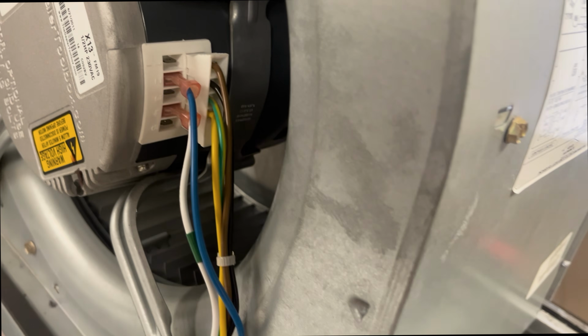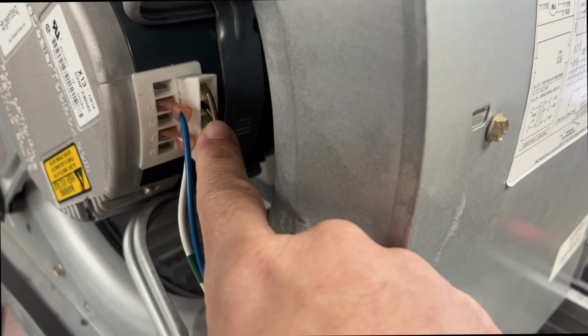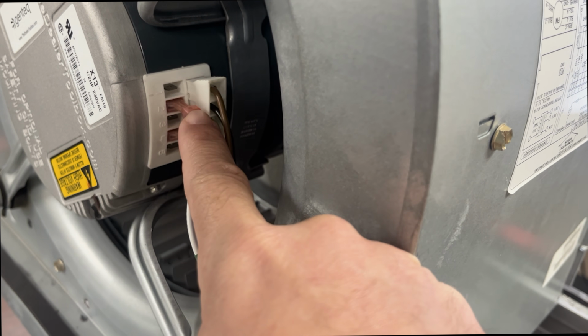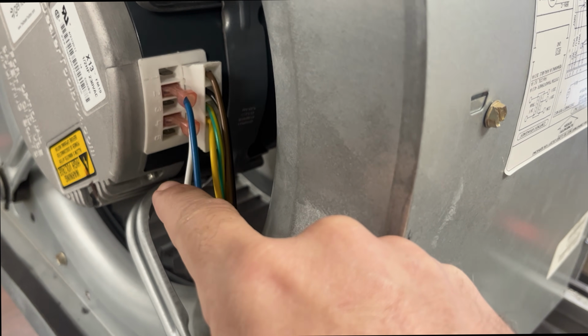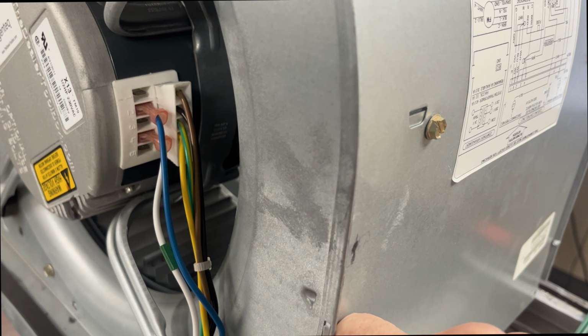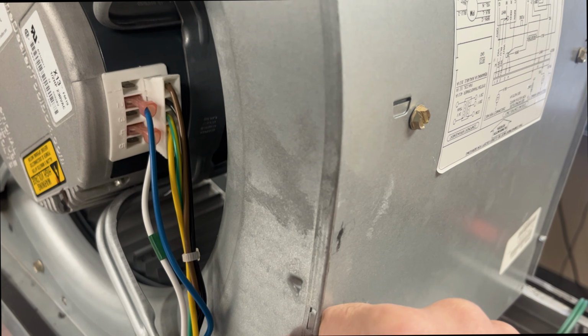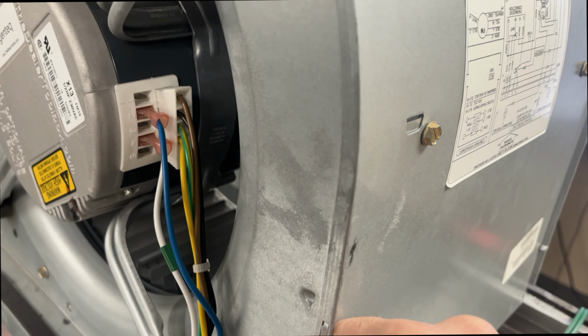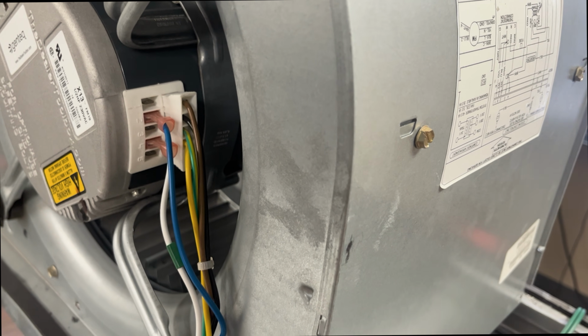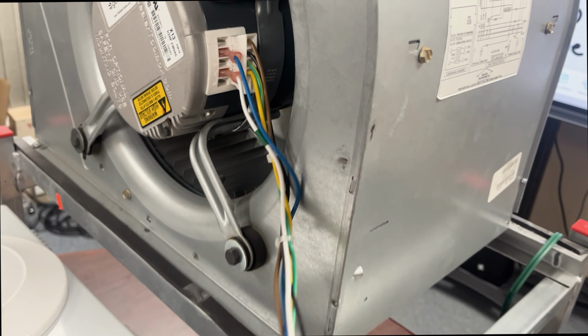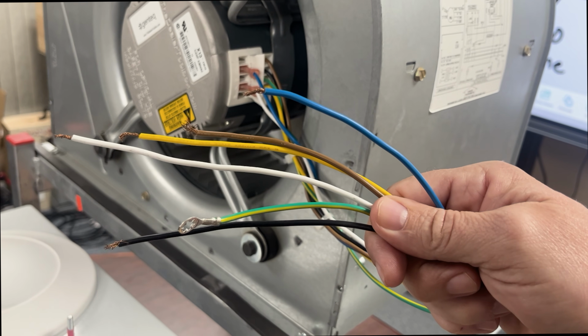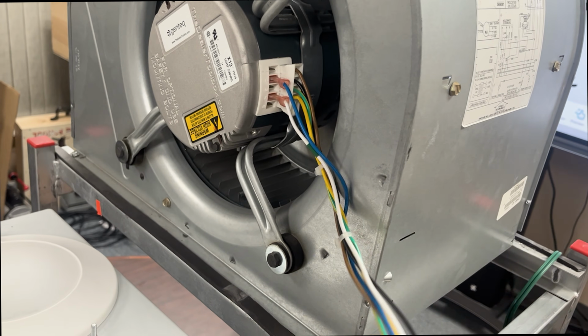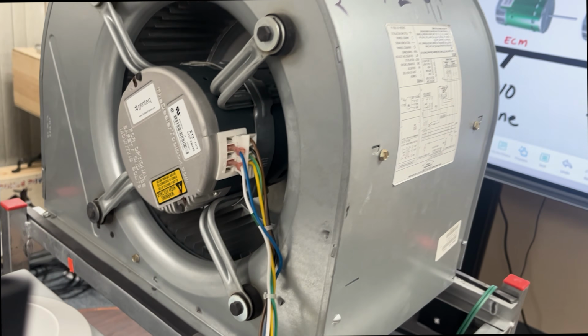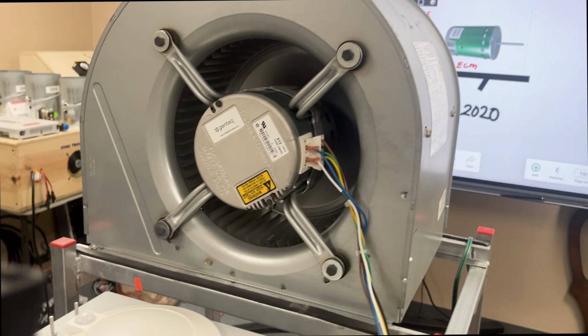If you look, this is already pre-wired. Now it's obviously not inside of an air handler, but you can see that we have a plug for our high voltage. And then we have our two connectors, the blue and the white, which are on terminal 2 and terminal 4. That's traditionally how you see it. And those are speed taps, and we're going to talk a lot about that. So I'm going to take advantage of having all these connected to the motor already. We're just going to touch them to our power supply, and we're going to get our motor to come on. And then we're going to discuss these speeds.